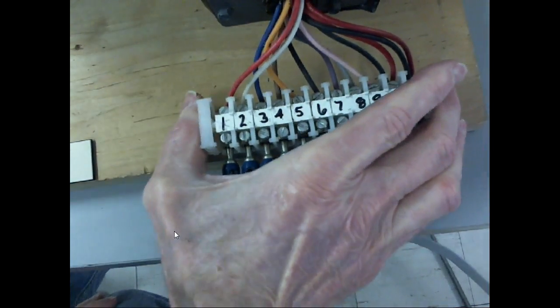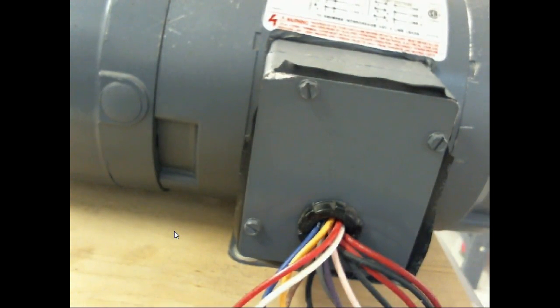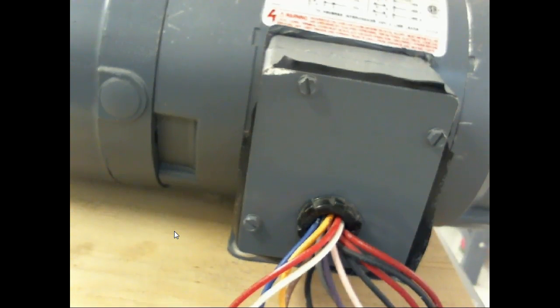Normally all this would be inside this panel, so the manufacturer's numbers would be in here. We'd pull these out and there'd be terminals to hook wires to, or a bunch of wires with metal rings with numbers on them. But there's a procedure in your textbook if you run into a 9-lead motor where people cut the metal tabs off to make the leads short, wire them at that instant, and then you're messed up because you come in with a problem and there's no leads on there at all.